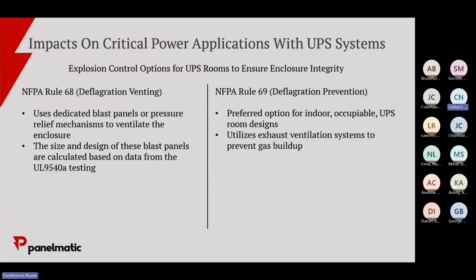So you'd asked before, what happens if someone goes up and you're trying to prevent arc flash? These deflagration panels are basically trying to channel that blast energy away from people and anything else, so if there's an event or propagation, people don't get hurt. Tying back to the real world example with the 8 firefighters, when they opened that door, it just blew out. The deflagration panels are designed to blow out of certain areas, not where someone would be standing, to try to contain that blast. But again, this is much more typical of a BESS design, not UPSs or UPS rooms.